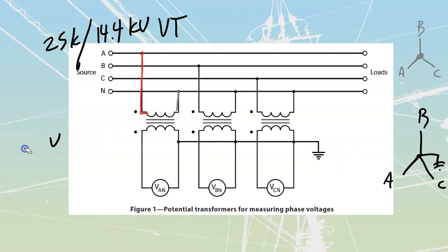This allows me to take individual phase readings, A to neutral. It's going to be scaled down from this one over here through the transformer ratio down to this one as well. So we've placed 3 individual voltmeter sections in there that are then going to give me the volts out. These are phase values of voltage, because I note that this is my star point going across here, here, and here, which means the star to an outside leg is just looking at a phase value.